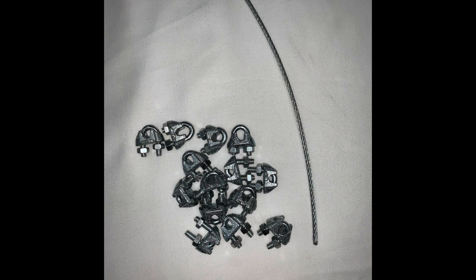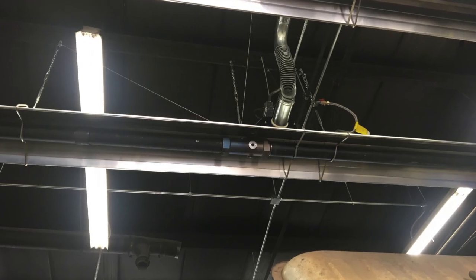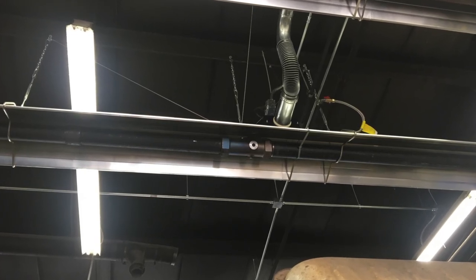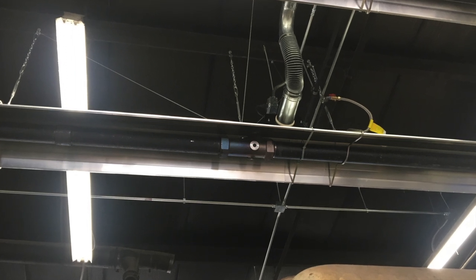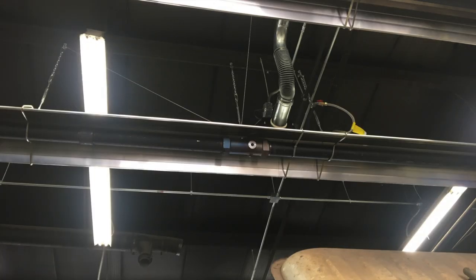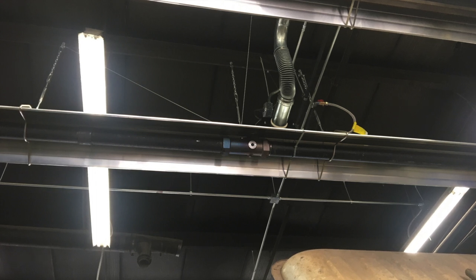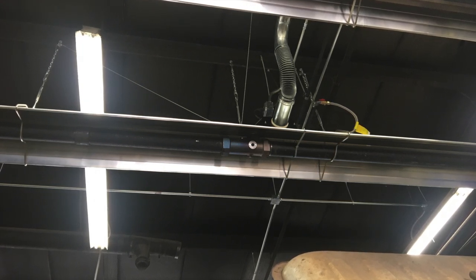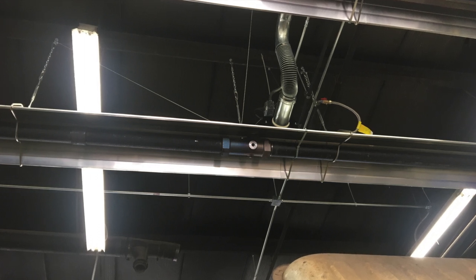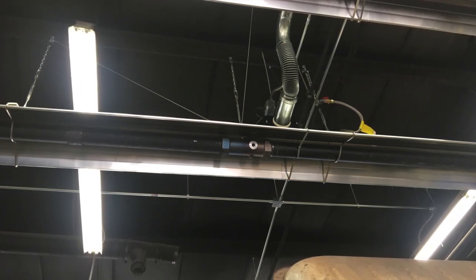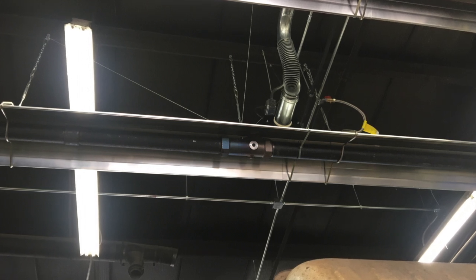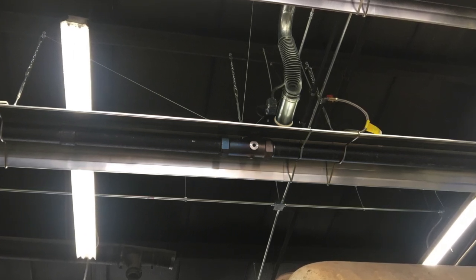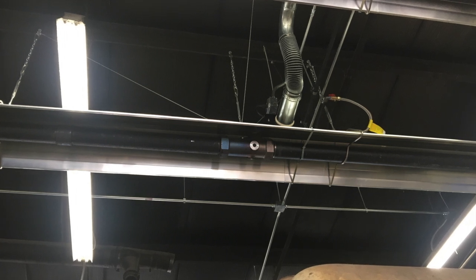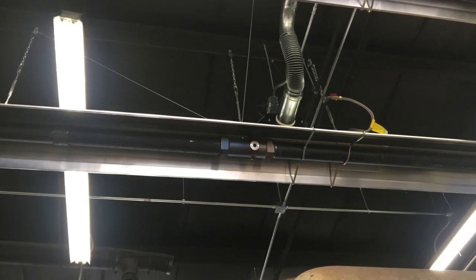One thing to remember, this system can expand 3 inches in 80 feet, so we must allow for that on the sway cables going with the system or parallel with the heat exchanger. Having the perpendicular sway cables taut and having the cable going with the pipe with slack so that the system can expand. The cable extending over the end of the pipe can be tight. As this system heats up, it will expand into them, putting slack into them and tightening up on the one you had slack in running over the system. The system can expand 3 inches in 80 feet.